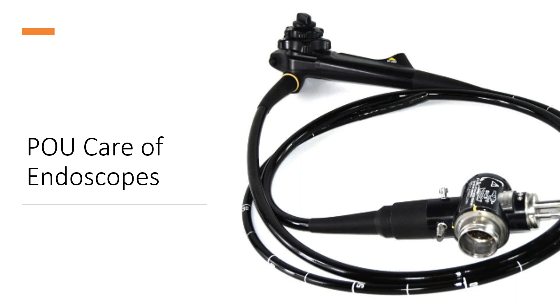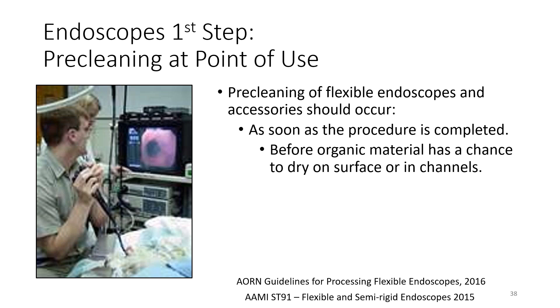So let's talk about endoscopes. Huge opportunity here. Pre-cleaning must be done at point of use. Pre-cleaning is spelled out really well with Olympus and endoscope manufacturers, but it should be done as soon as the procedure is completed and before the organic material has a chance to dry on the surface or in channels. And this comes right from AORN and AAMI ST91.